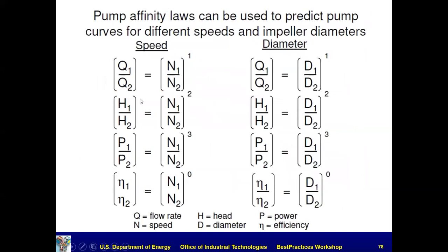So anyway, this says that if I cut the speed in half, I cut the flow in half. If I double the speed, I double the flow. So the head then is that ratio of speed, which is the ratio of flow, squared, and the power of that point goes with the cube. And then the efficiency is to the zero power, which means the efficiency stays the same.